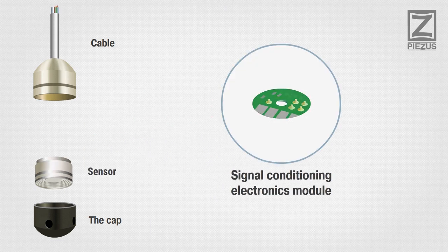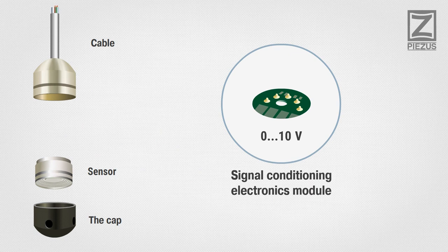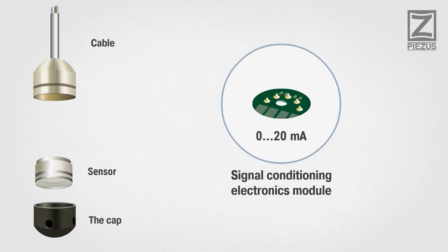The Signal Conditioning Electronics Module converts the sensor signal into standard normalized electrical output, such as 4 to 20 milliamps, 0 to 10 volts, or 0 to 20 milliamps. Various models are also capable of digital communication using HART or Modbus protocols.